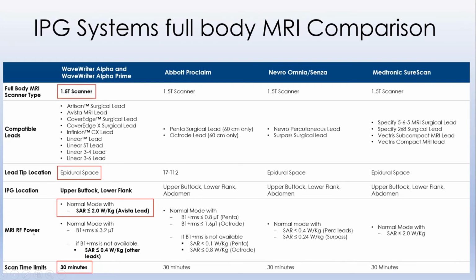As for the MRI radio frequency power, in normal mode, if you use the Avista lead with the Alpha, you can go to normal mode with a SAR of 2.0 watts per kilogram. If you don't have those possibilities to calculate the mean square roots, and you use the older type of leads, then you have to decrease the SAR down to 0.4 watts per kilogram if you connect it to the Alpha, and then it will be full body MRI conditional. And the scan time limit, as you can see, is 30 minutes for all companies.